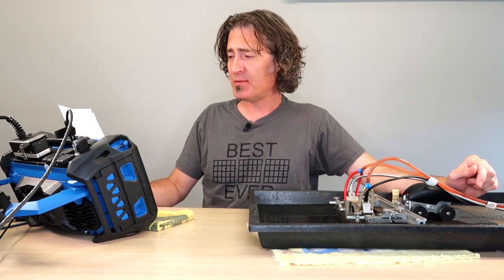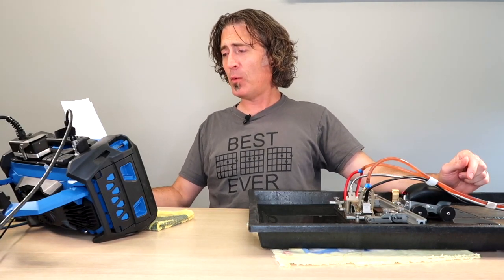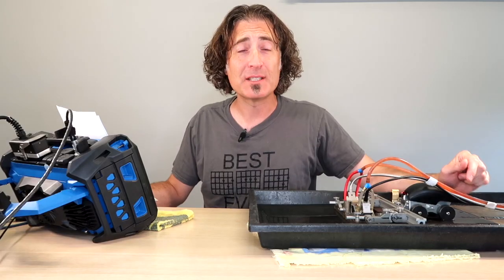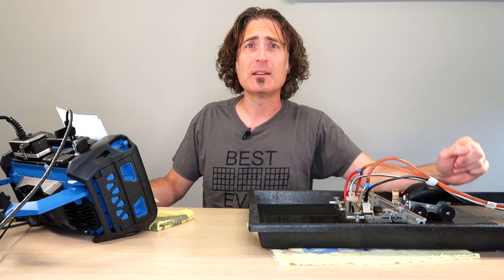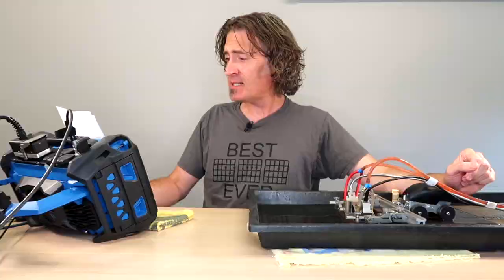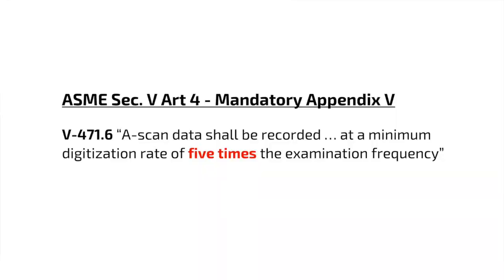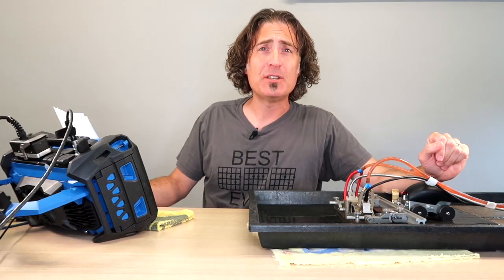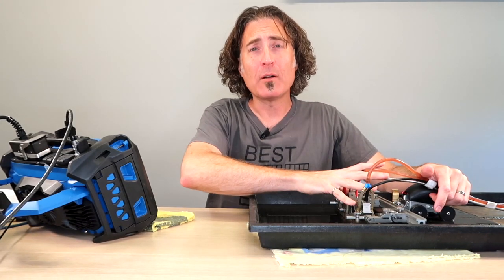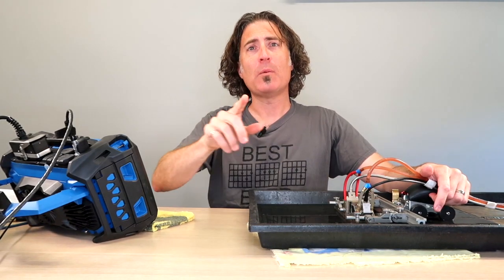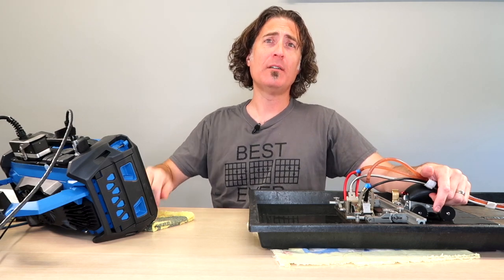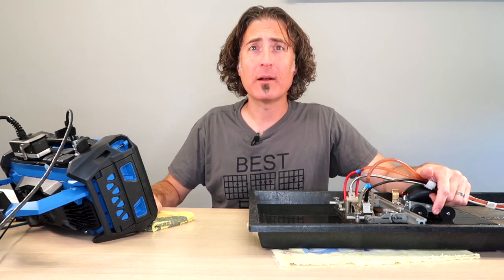ASME Section 5, Article 4, Mandatory Appendix 5 for encoded phased array, boy, that just rolls off the tongue, doesn't it? It states that A-Scan data shall be recorded at a minimum digitization rate of five times the examination frequency. That means with 5 megahertz transducers, they want to see a net digitization rate of 25 megahertz.